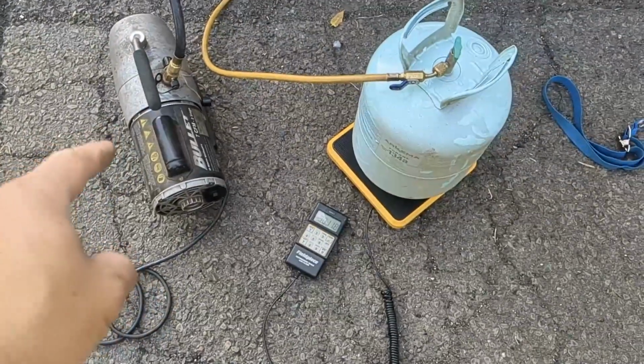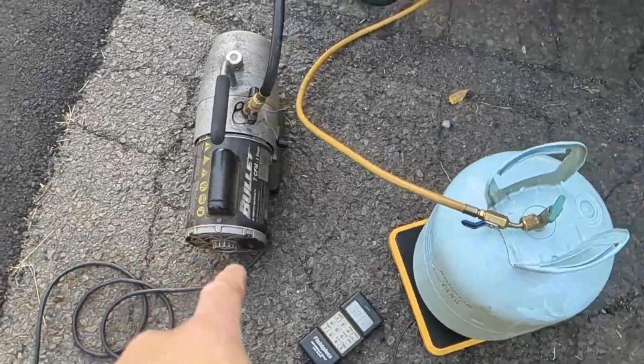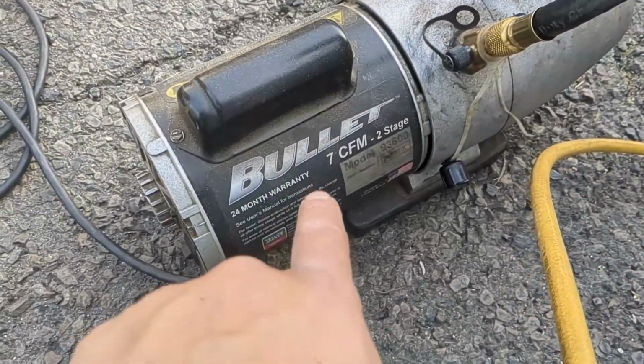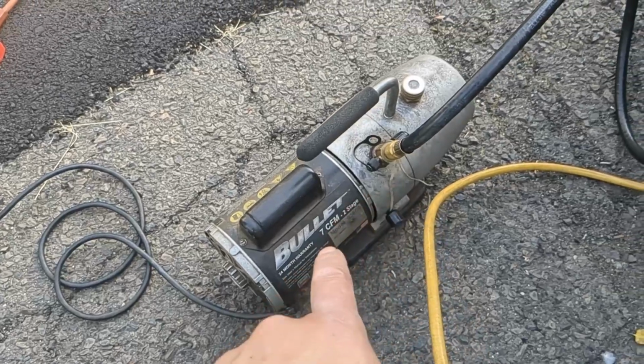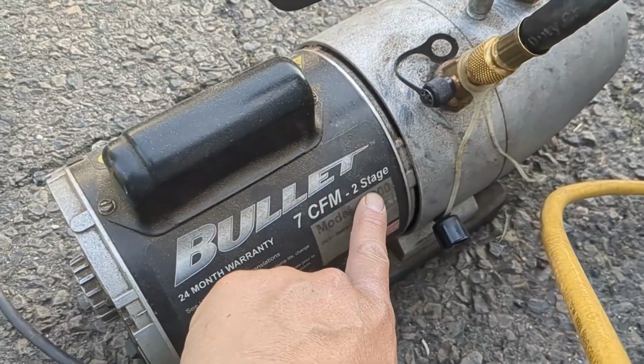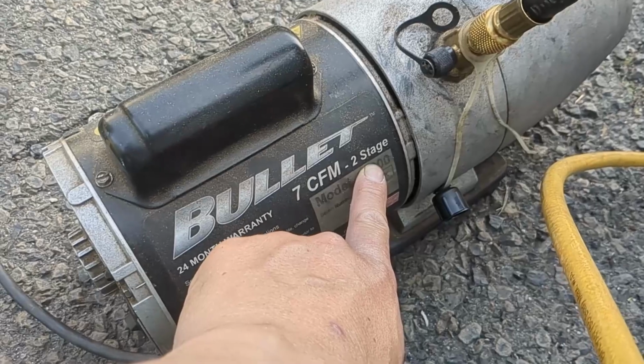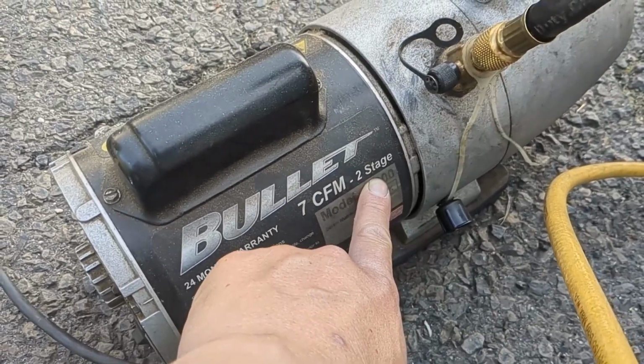Anyways, this is just the standard vacuum pump, the Bullet 7 CFM 2-stage. Make sure if you want to get a vacuum pump, it's 2-stage. A 1-stage is garbage.